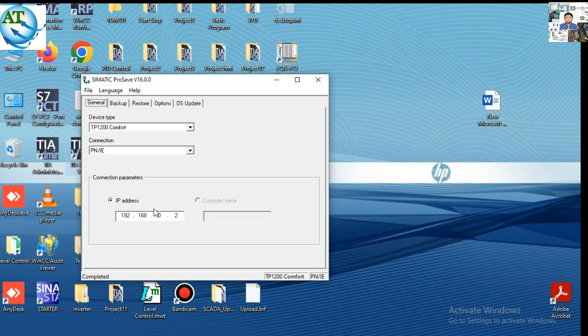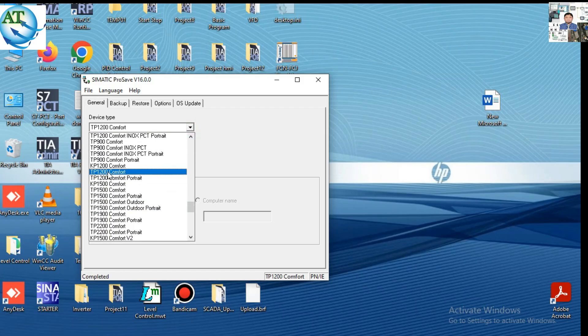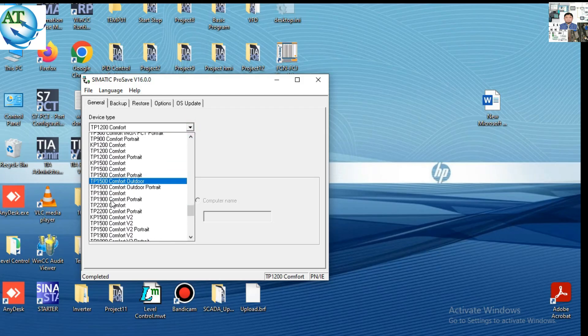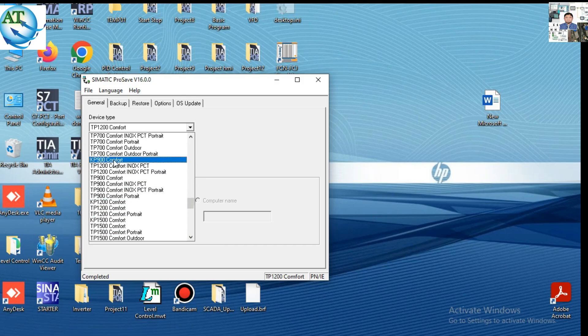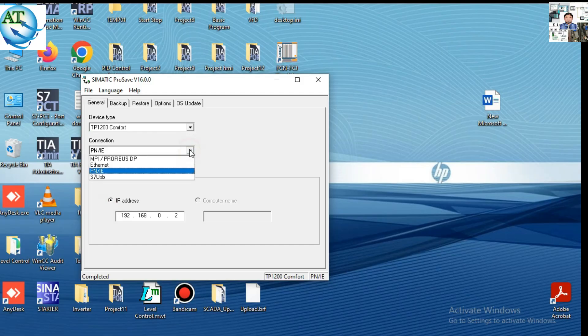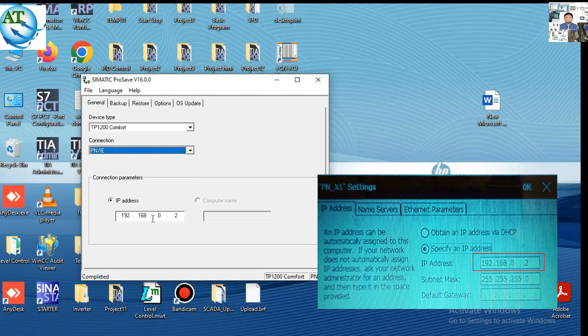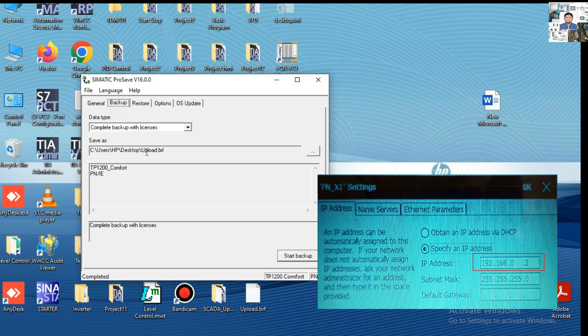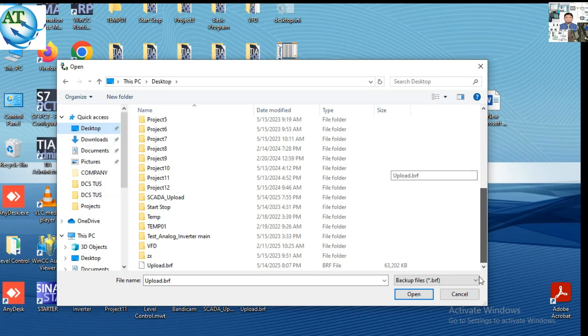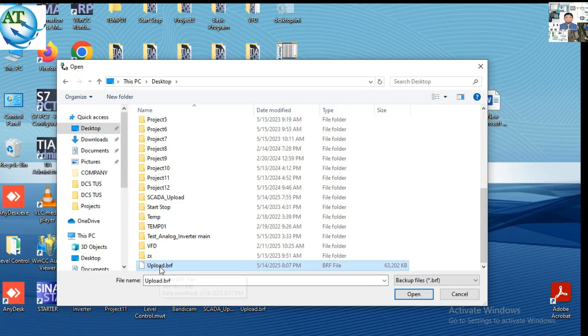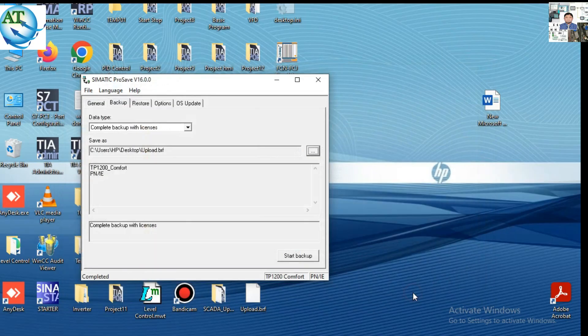If your PC IP address is not in the same series — 192.168.0 — you need to change it. Then go to the search button and find the SIMATIC ProSave software. In ProSave, you can find your desired device, the TP1200 Comfort. Select it. Then go to the connection type — industrial Ethernet — and select it. The IP address must be the same. Enter the IP address, then go to the Backup button. Select where you want to save the upload program, then press the Start Backup button.